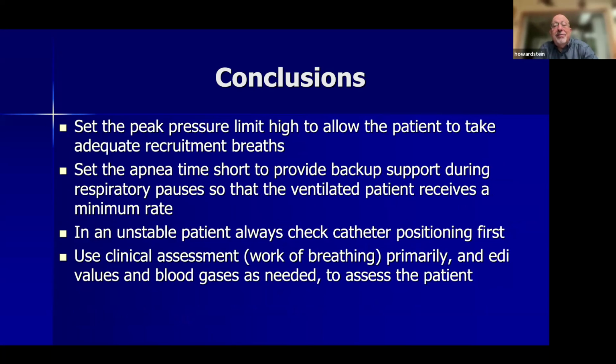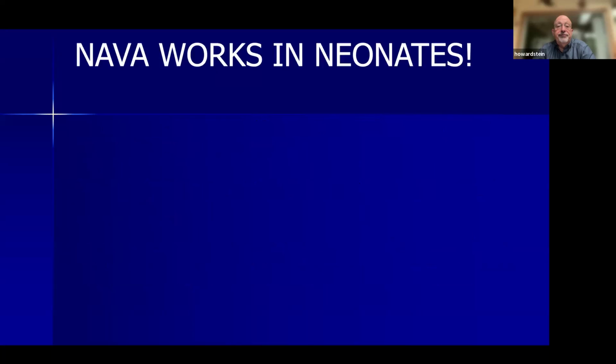Set the peak pressure limit high to allow the patient to take adequate recruitment breaths. Set the apnea time short to provide backup support during respiratory pauses so that the ventilated patient receives a minimum rate. If the baby's unstable, always check the catheter positioning first and use your clinical assessment, your work of breathing primarily, and then your EDI values and blood gases secondarily when you're assessing the patient.